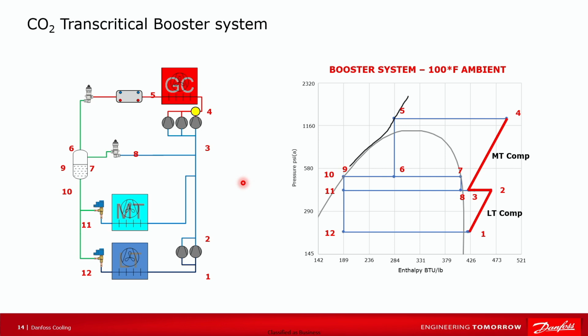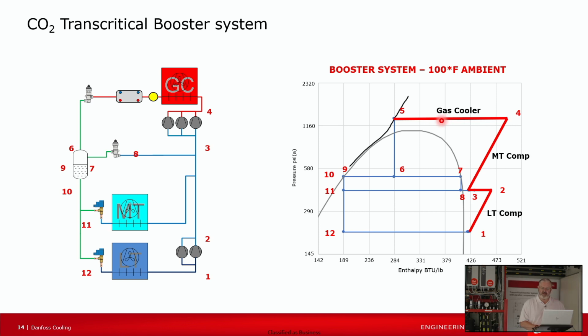We're at the inlet of the gas cooler. And again, we're on the high side of our system, 100-degree ambient and supercritical mode. We go across the gas cooler, and all we're really doing on a 100-degree day is desuperheating. That's where the term gas cooler comes from. When you're above the critical point inside the gas cooler, you're not condensing, so the term condenser isn't really applicable. Since it's desuperheating, they call it a gas cooler.